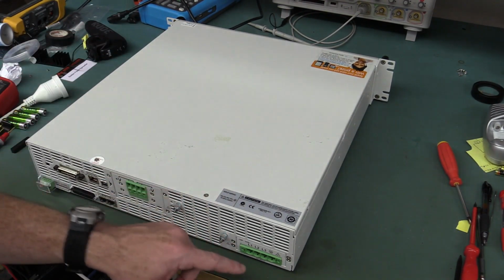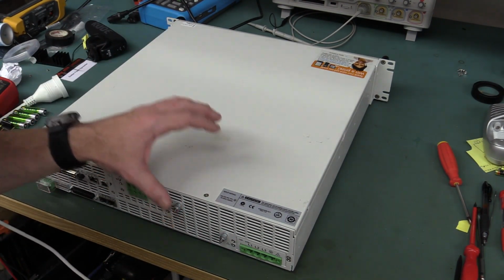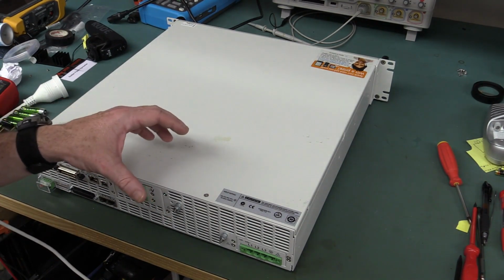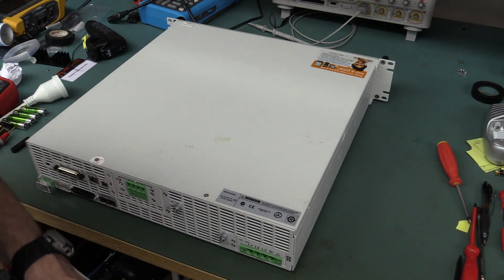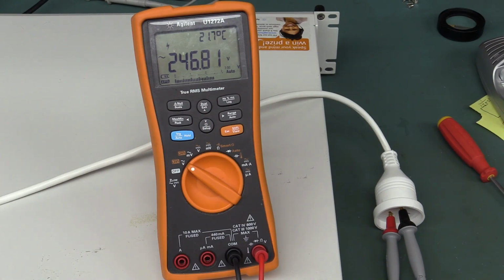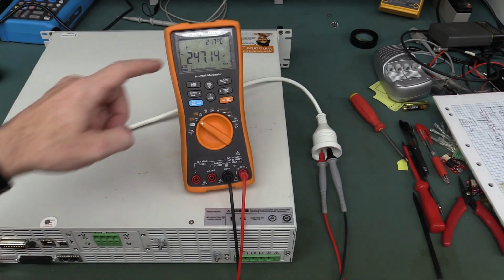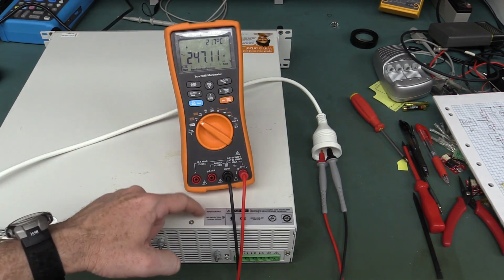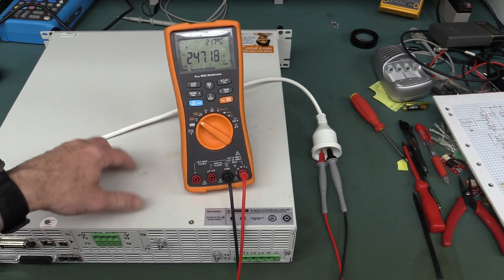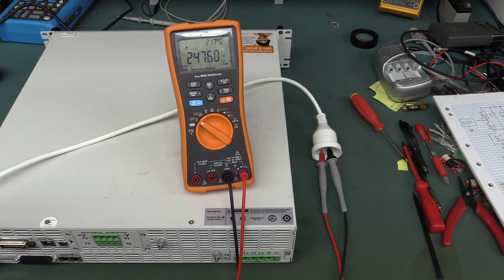Actually, technically, I would not do that here in the lab because my lab voltage is actually 245 volts at the power point. And actually, I'll prove that. And there you go, I'm pretty close to 247, so that's almost at the extreme limit of what they're allowed to give us here. So not necessarily such a good thing. Even though it's only 7 volts over the nominal upper rated limit of 240 volts, and it'd probably work, I'd be incredibly surprised if it was an issue. Still, just as a matter of course, you wouldn't do it. So for troubleshooting this thing, I would use my adjustable mains power supply.